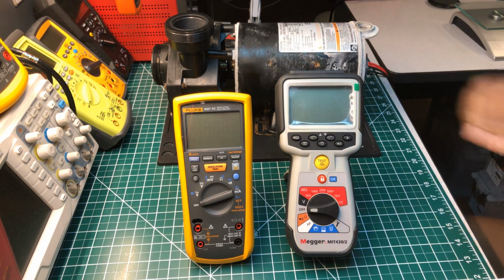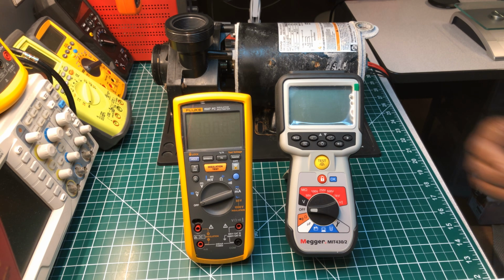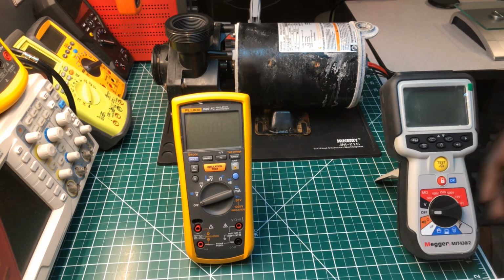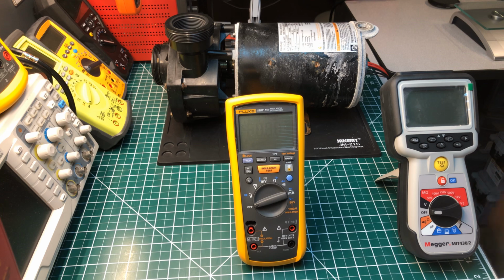Starting with the FLUKE 1587, some of the megohmmeter features: the test voltage ranges from 50, 100, 250, 500, and 1,000. The insulation resistance range is 0.001 megohms to 2 gigaohms.